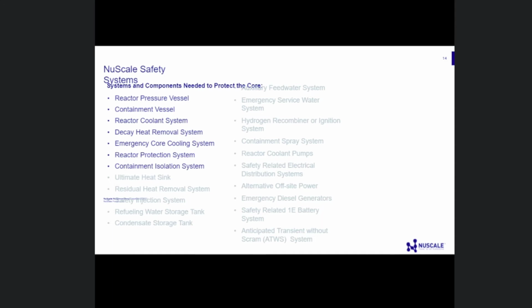Now, for NuScale, shown in the dark items, the only real digital component is the reactor protection system, which we build from a programmable gate array so it can't be reprogrammed in the field, you'd have to ship it back to the factory. There's some tunable elements we have to protect, but the actual logic that shuts down the plant if something goes wrong is an FPGA or similar technology.